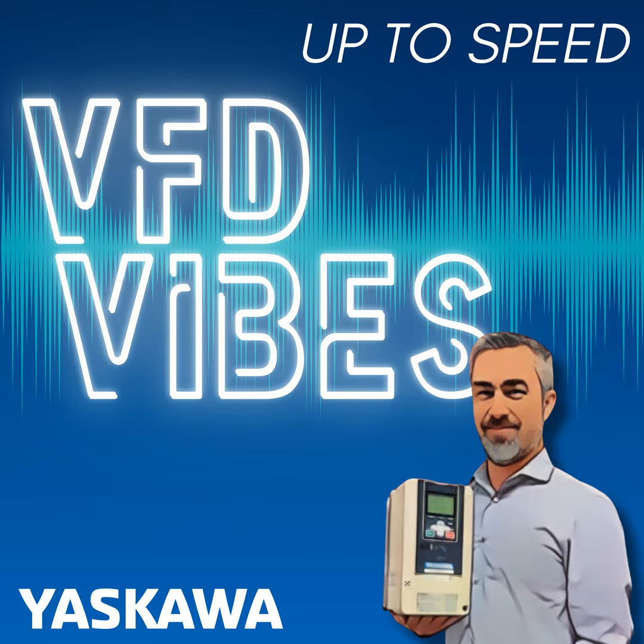Now, we also have other voltages. We have 208 that's sort of common on the East Coast. We have 600 volts, which is common in Canada. But almost all installations in the United States are 480 volt three-phase, and 480 volts is defined as the line-to-line voltage. All those voltages you mentioned are line-to-line because, again, by default, there is no neutral to even measure to.